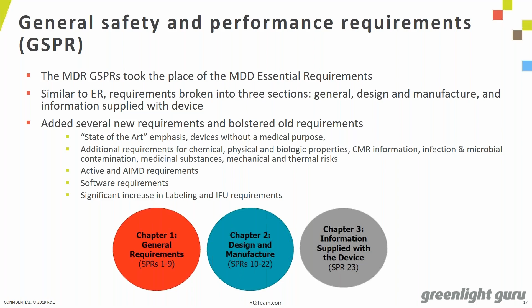So Section 1 under general requirements is very similar to the essential requirements from the MDD. Some of the key differences are the emphasis on risk management and state-of-the-art assessments, intended to ensure that compliance is maintained over time and not just a one-time evaluation that you set and forget. But this section should look similar to the directives.